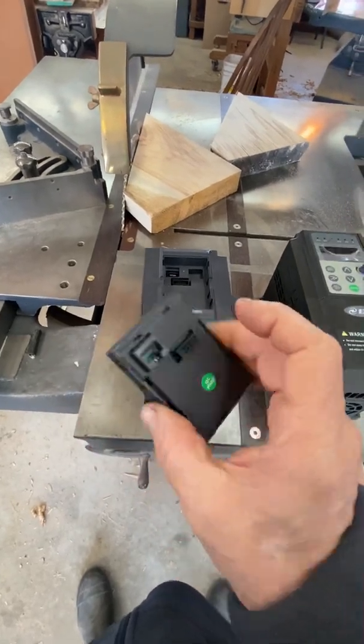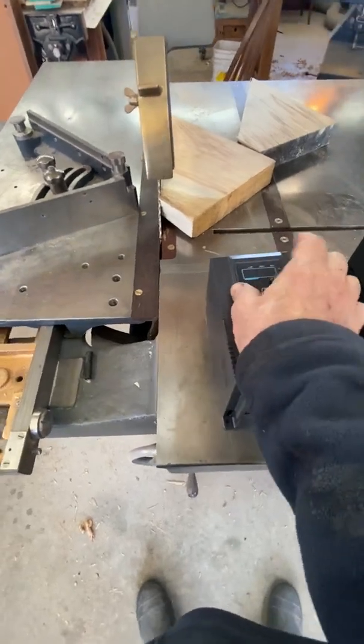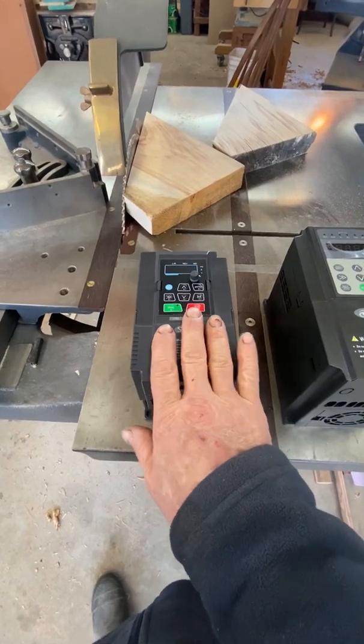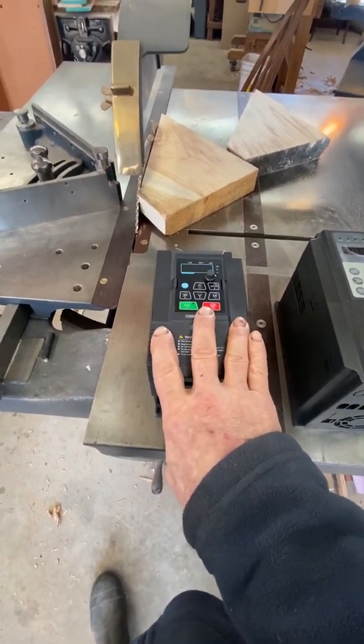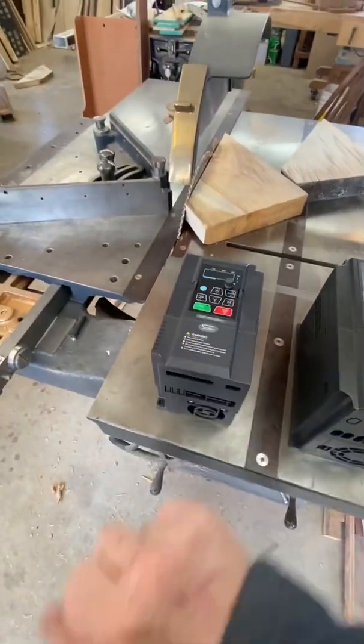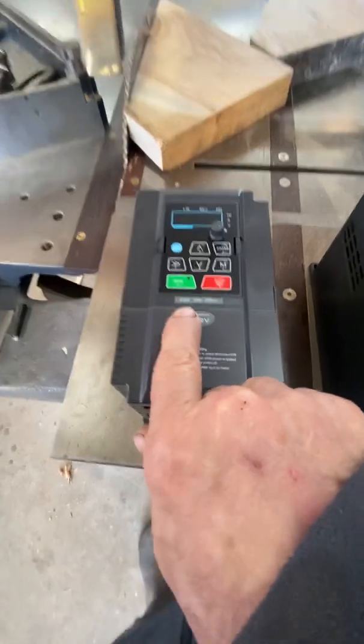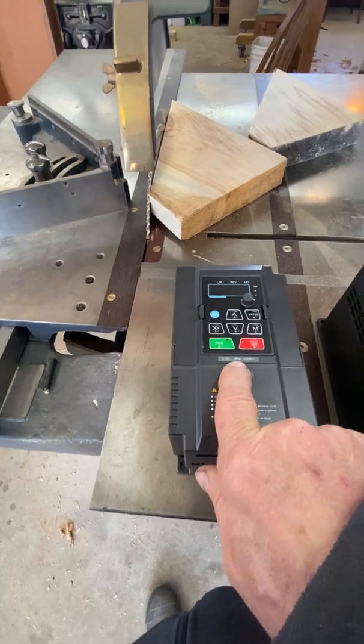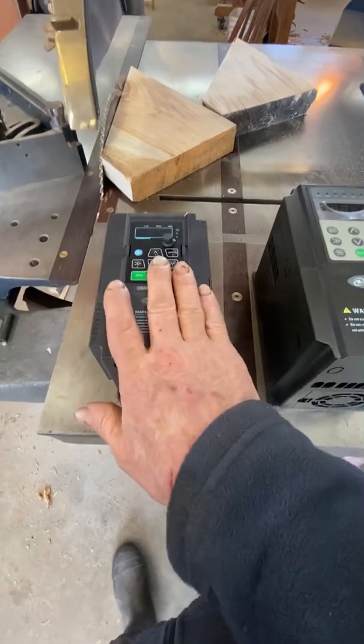For you Americans, that's 15 feet, so you can have your VFD placed anywhere you want. These operate up to two horsepower on a 15-amp standard 120-volt plug, but if you supply your plug with 30 amps, this will operate up to a three horsepower unit. It's a very robust unit — it's 2.2 kilowatts and it is single phase input.